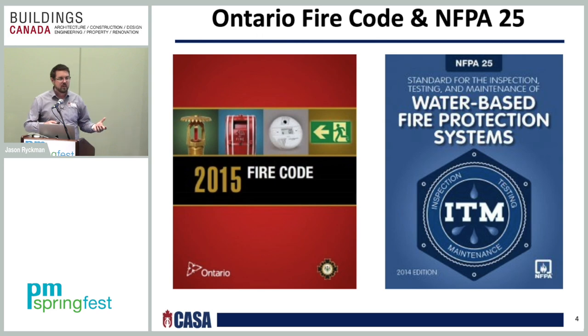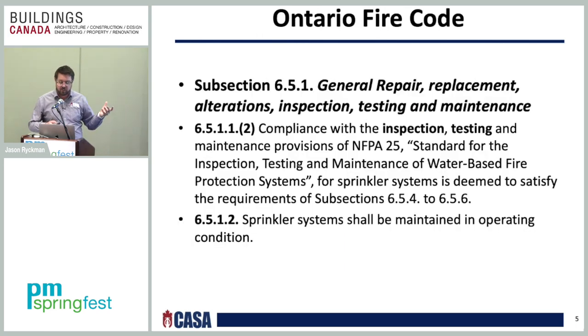Now, whenever you use the Ontario Fire Code, it's a little different. The Ontario Fire Code basically states that compliance with inspection, testing, and maintenance provisions of NFPA 25, which is a standard for inspection, testing, and maintenance of water-based fire protection systems, for sprinkler systems is deemed to satisfy requirements in section 654 to 656. So the Ontario Fire Code gives you an option. It gives you an option of either using the fire code throughout or using the NFPA 25 document for section 654 to 656 only.